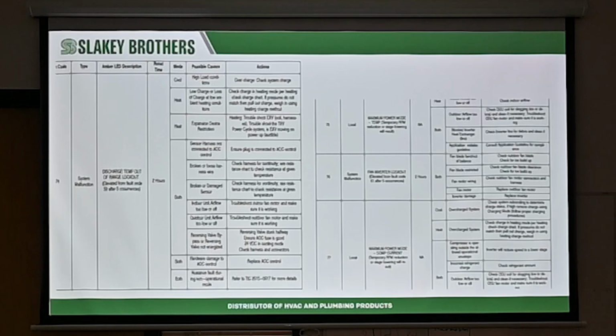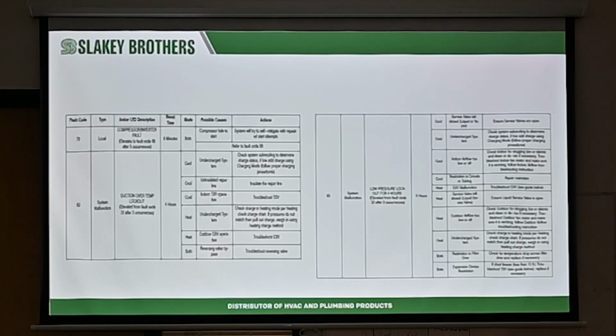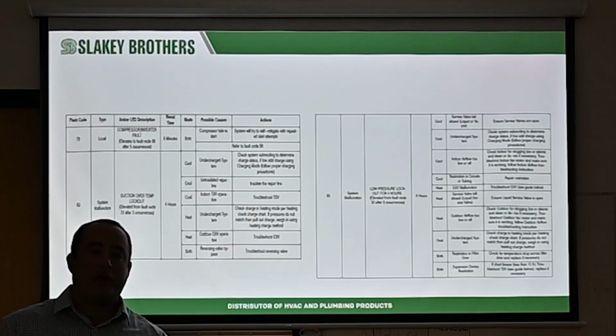But a lot of it is, you're going to ohm out the condenser fan motor, you're going to ohm out the compressor, and especially if it's telling you there's something wrong with the board or something wrong with the compressor. I mean, that's what it really comes down to. When you really read it on some of these faults, it basically means either both things are bad, or there's something wrong with my inverter board, or something wrong with my compressor. And at that point, you can make the call. What can you get quick? You may want to order both. Be prepared. Or just order the new board, replace everything, get it going, and if you get the same fault code, replace the compressor.